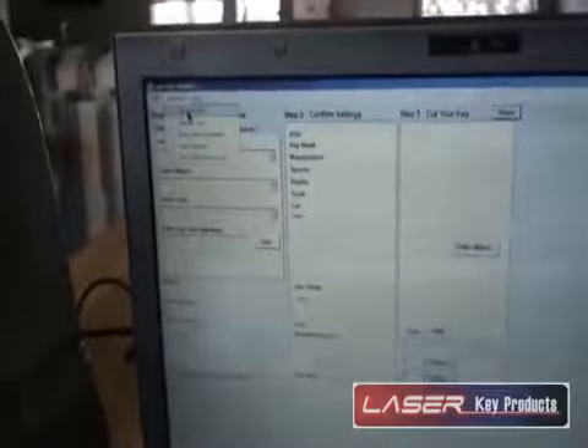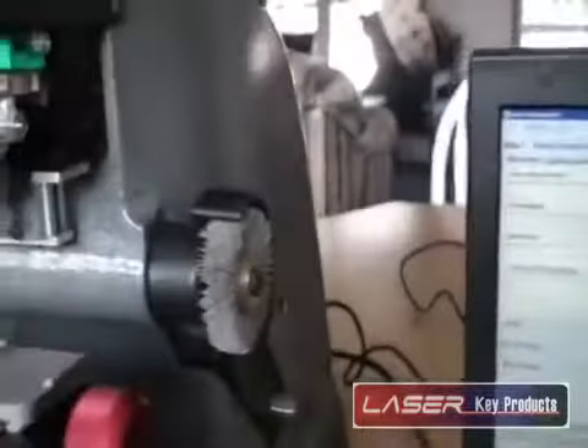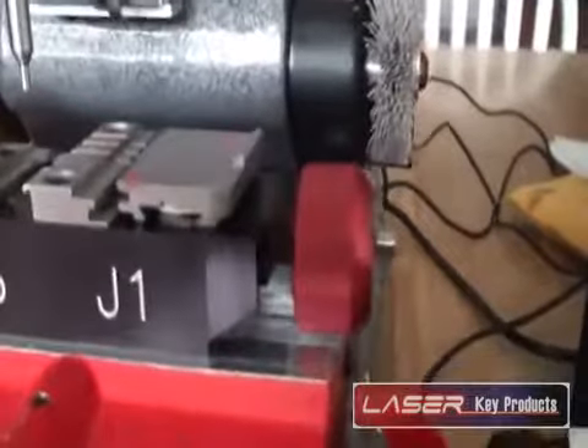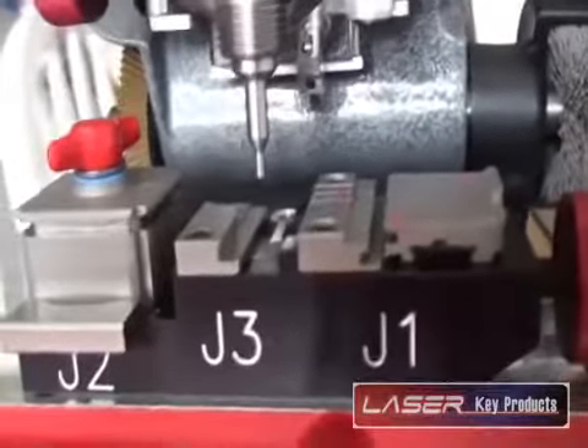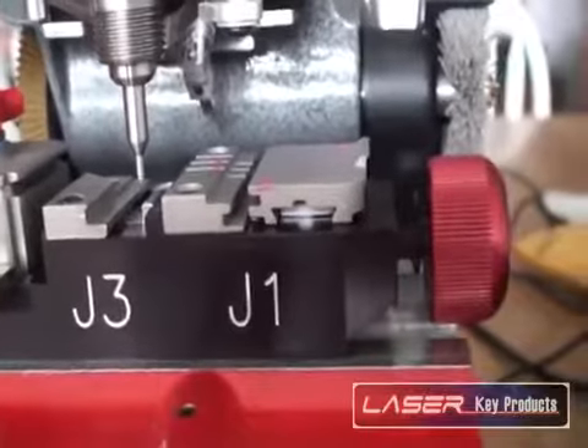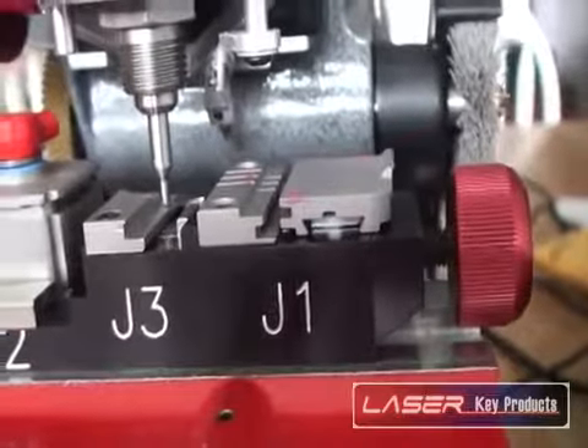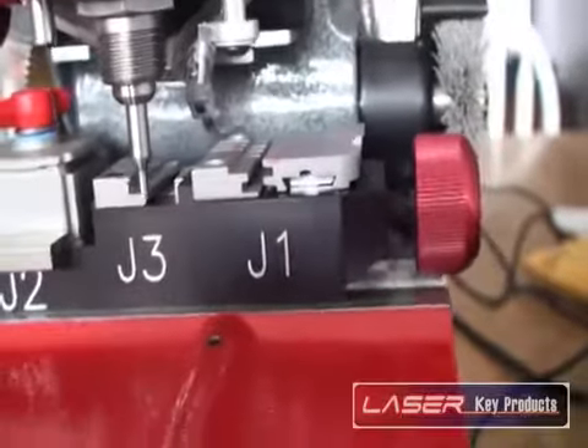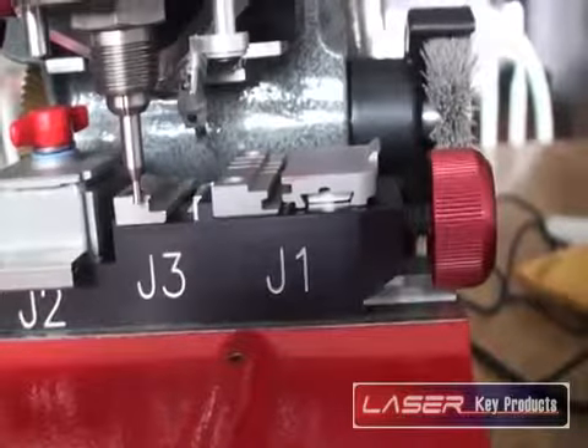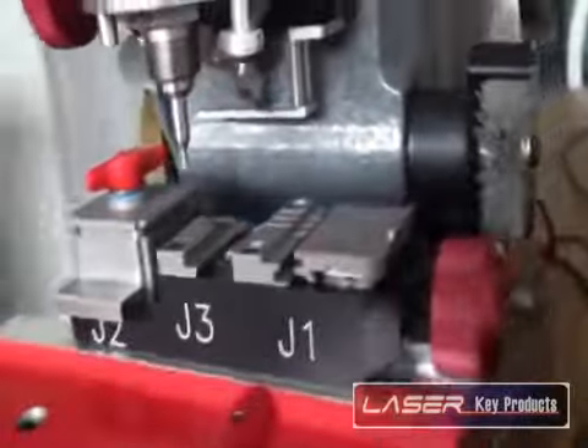Next thing I want you to do is go to operations, calibrate cutter, and this time we're going to do jaw 3. We do jaw 3, say OK, and again it'll go over and come down and touch off on the very far edge of the jaw. It'll go to the right, touch that, come to the front, drop down and over, back up, and now that portion of it is complete. And once again, it is in an update in progress, 30 seconds or so. Once it's done, you can click on OK, and that's done.